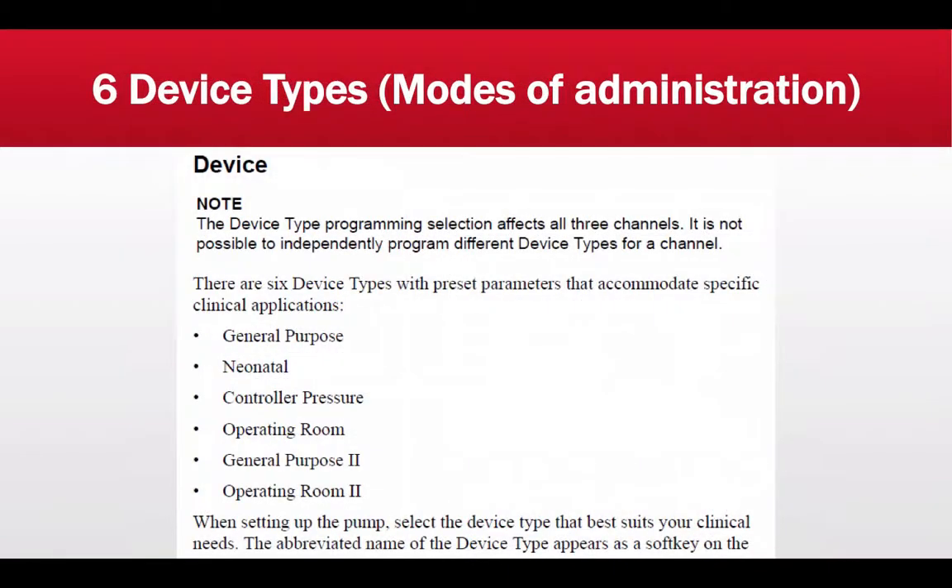The Med System 3 by CareFusion facilitates six device types or modes of administration. These are preset parameters that accommodate specific clinical applications: general purpose, neonatal, Controller Pressure, operating room, and general purpose 2, as well as operating room 2.